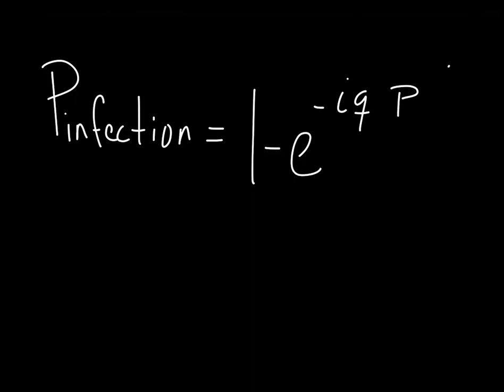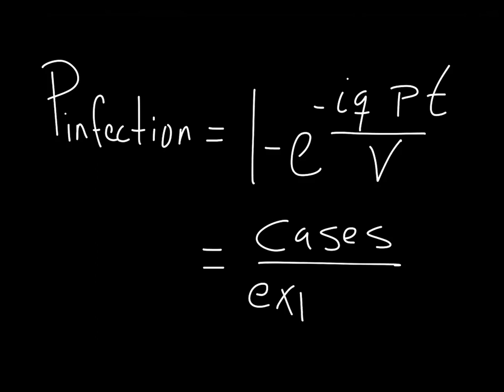The number of infectious individuals times the generation rate is then multiplied by the breathing rate of the exposed individuals and the duration of exposure. This value is divided by the ventilation rate of clean air in the space. The resulting percentage can also be expressed as the ratio of potentially affected individuals to the number of exposed individuals.